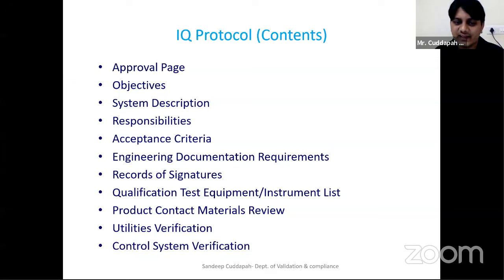Then you give the acceptance criteria, what your requirement is, and whether that acceptance is met or not, you verify in the actual installation qualification report. Then you have the engineering documentation requirements, then records of signatures. Whoever is going to participate in this qualification, their records of signatures will be taken first, stating that these persons are trained on this qualification and have the authority to execute this installation qualification. That kind of training records will be attached to this qualification.